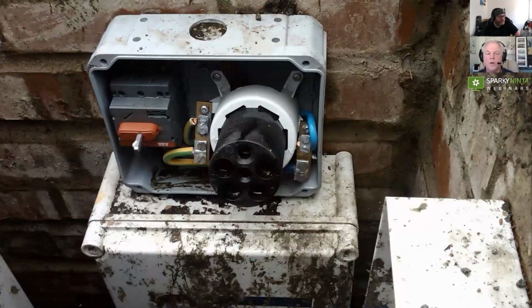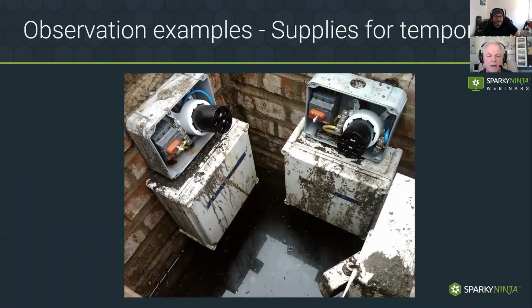Fortunately we'd been called in and took the box off the bottom. If you look at the bottom covers, the armoured cables come into the bottom enclosure, where the armouring is terminated. Was the armour a bit rusted? It was rusted to heck - on one of these we had an earth loop impedance of about 65 ohms.